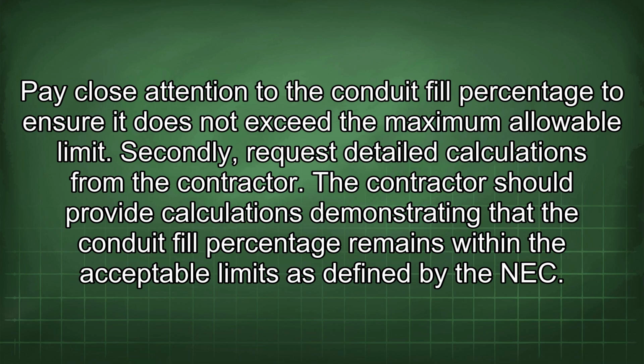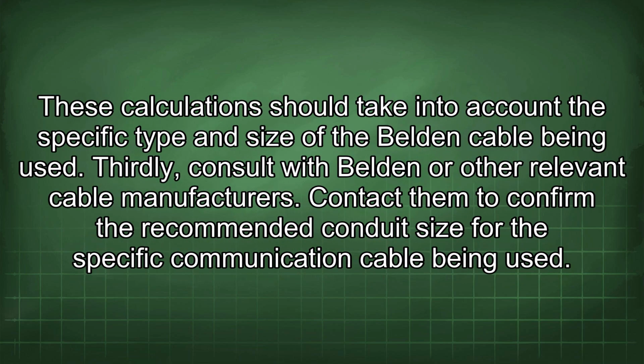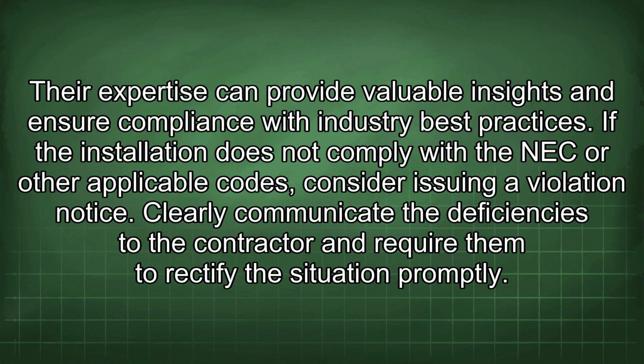Secondly, request detailed calculations from the contractor. The contractor should provide calculations demonstrating that the conduit fill percentage remains within the acceptable limits as defined by the NEC. These calculations should take into account the specific type and size of the Belden cable being used. Thirdly, consult with Belden or other relevant cable manufacturers. Contact them to confirm the recommended conduit size for the specific communication cable being used. Their expertise can provide valuable insights and ensure compliance with industry best practices.